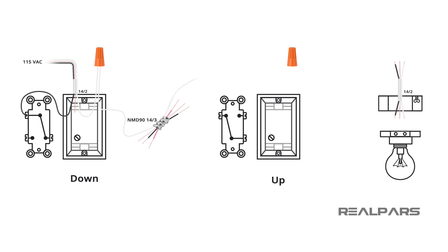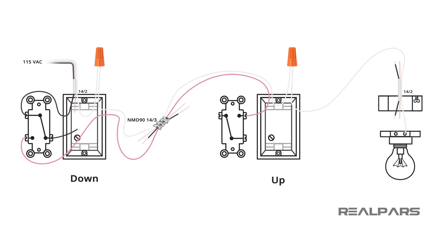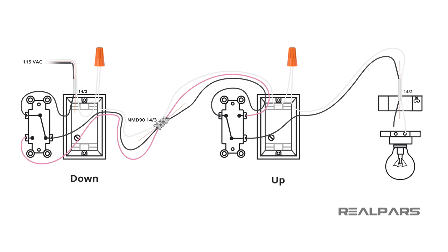There is another wire connector securing the 14-3 white wire to the 14-2 white wire of the light cable. This wire connection is completed inside the up switch electrical box. The 14-3 cable connects the two switches. The red wire connects the switches' normally open terminals, and the black wire connects the normally closed terminals. Finally, the black wire of the light electrical box connects to the up switch common terminal.